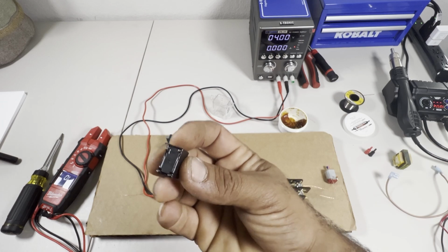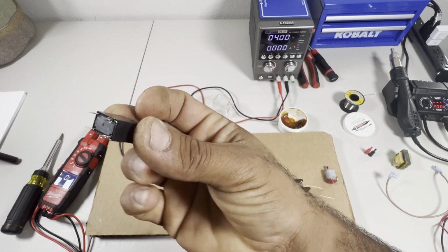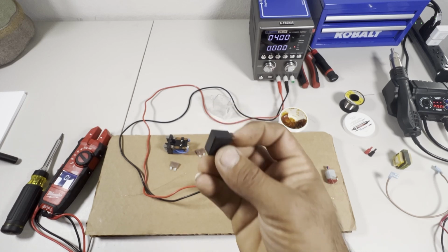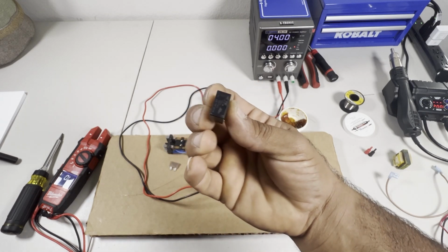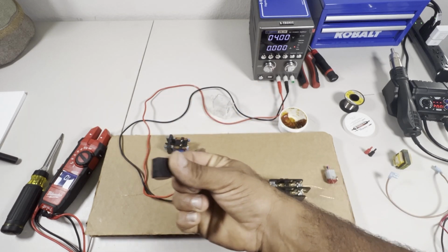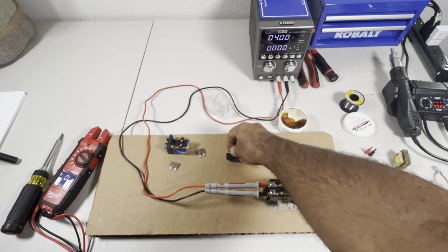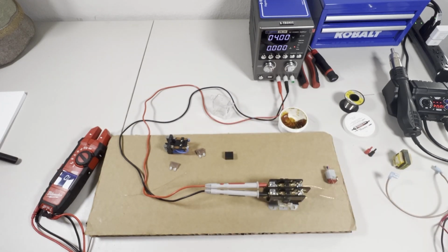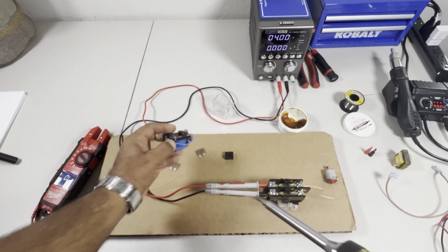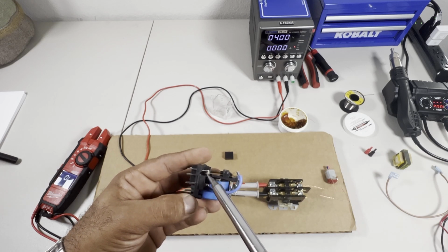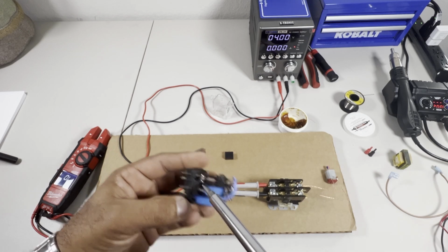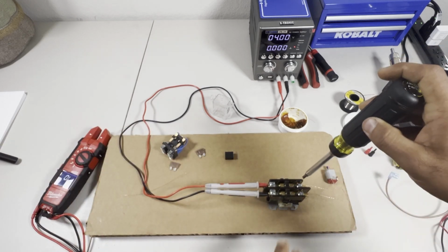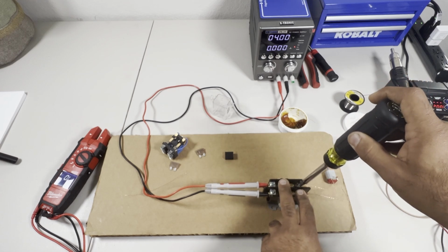The main reason these relays are sealed from the factory like this is because of that. The less moisture and dust and everything else you have inside it, the longer these relays are going to last. Now, what happens when this area gets arced out and blacked out? This is what's going to happen to the relay.